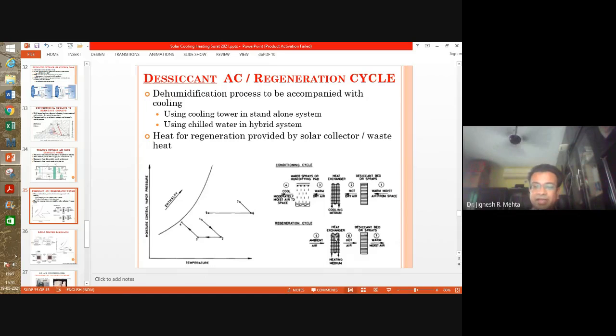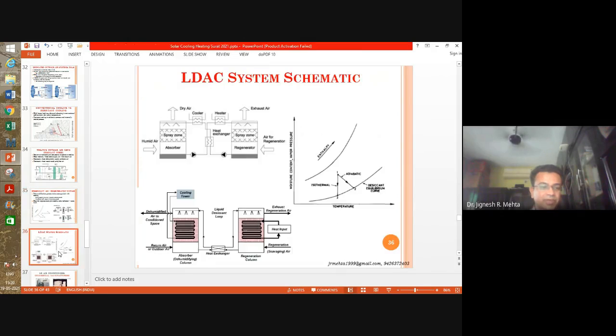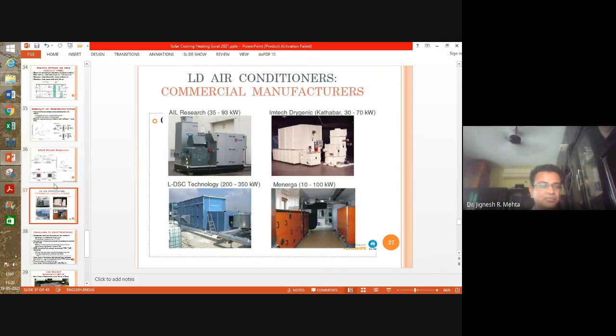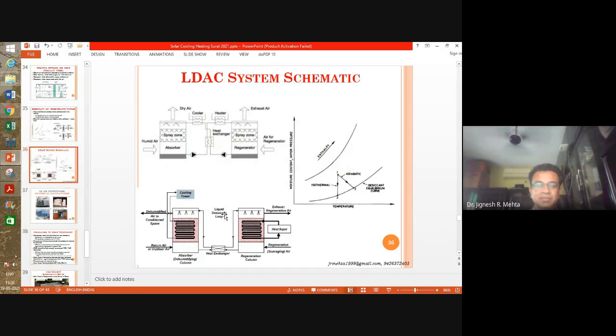But then on the other side, you have to take away moisture from the desiccant so that you are able to work in a cycle. So this is the regeneration process, right? If you are going for liquid desiccant based systems, then I'll explain only this diagram. As you can see, the return or outdoor air is treated here, and this is the spray of liquid desiccant, something like a cooling tower, but internal cooling is also provided. Such adiabatic towers also can be there, but theoretically internal cooling is a better idea.